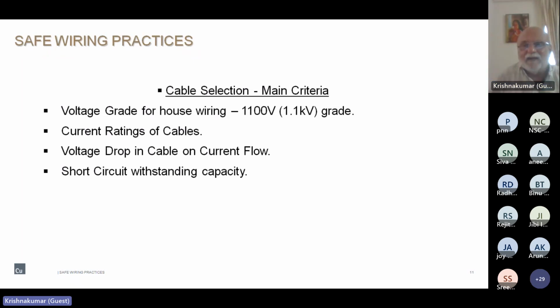When I talk to the wireman, I tell him, you just blindly take the next step of wire after you calculate with the load and factors. If you find that 1.5 is the cross section by your calculation, take 2.5 instead. Somewhere it is 2.5, go to 4. In other words, you are derating the wires and using them. This is one principle which will save a lot of troubles in a building.